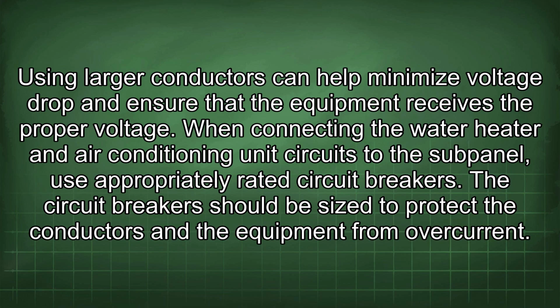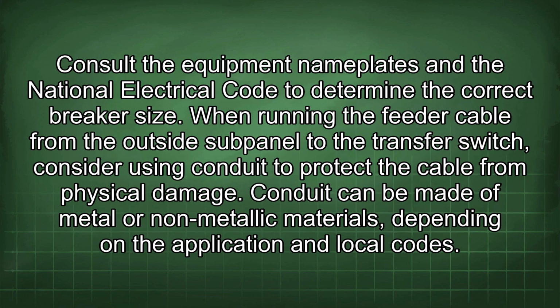When connecting the water heater and air conditioning unit circuits to the subpanel, use appropriately rated circuit breakers. The circuit breakers should be sized to protect the conductors and the equipment from overcurrent. Consult the equipment nameplates and the National Electrical Code to determine the correct breaker size.